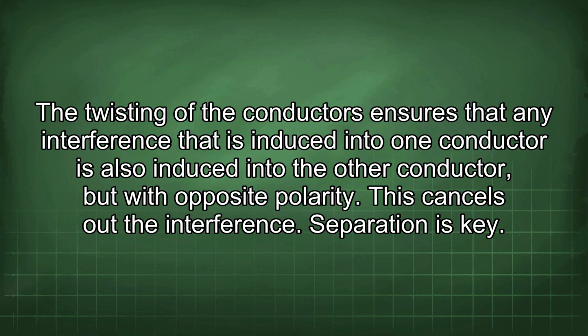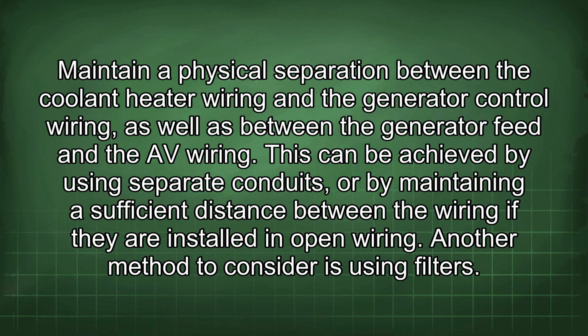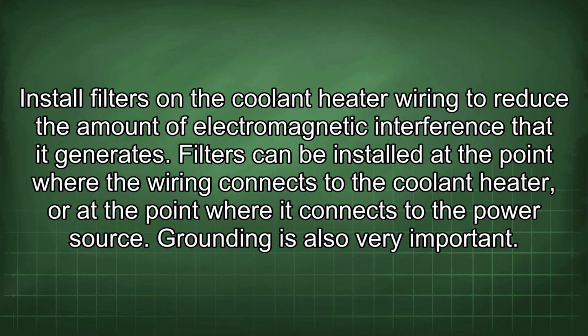Separation is key. Maintain a physical separation between the coolant heater wiring and the generator control wiring, as well as between the generator feed and the AV wiring. This can be achieved by using separate conduits, or by maintaining a sufficient distance between the wiring if they are installed in open wiring. Another method to consider is using filters. Install filters on the coolant heater wiring to reduce the amount of electromagnetic interference that it generates. Filters can be installed at the point where the wiring connects to the coolant heater or at the point where it connects to the power source.